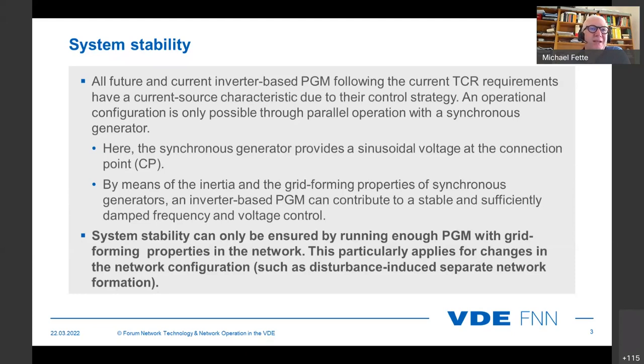In general, the synchronous generator provides a sinusoidal voltage at the connection point, and that means, as we discussed in some lessons before, the sense of inertia and grid forming properties of the synchronous generators. And the inverter-based PGMs can contribute to a stable and sufficiently damped frequency and voltage control. At the end, system stability can only be ensured by running enough PGMs with grid forming properties in the grid. This particularly applies for changes in the network configuration, such as disturbance-induced separate network formation. So the question is how many of these non-stability-supporting PGMs we allow within the grid and how many of the others we need.